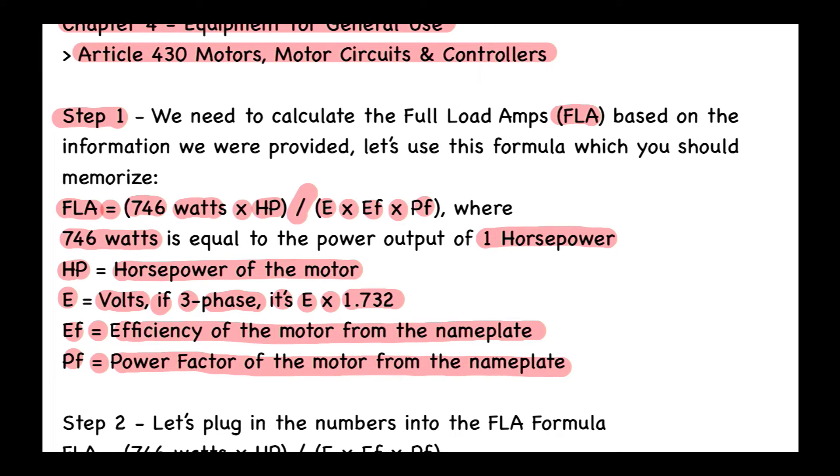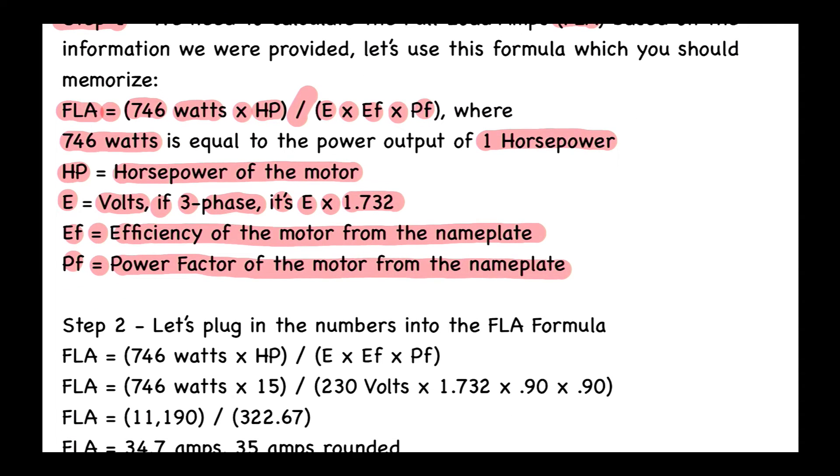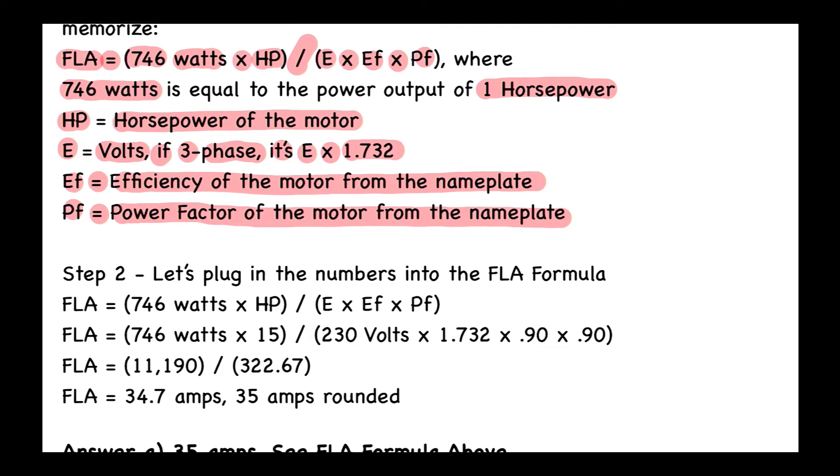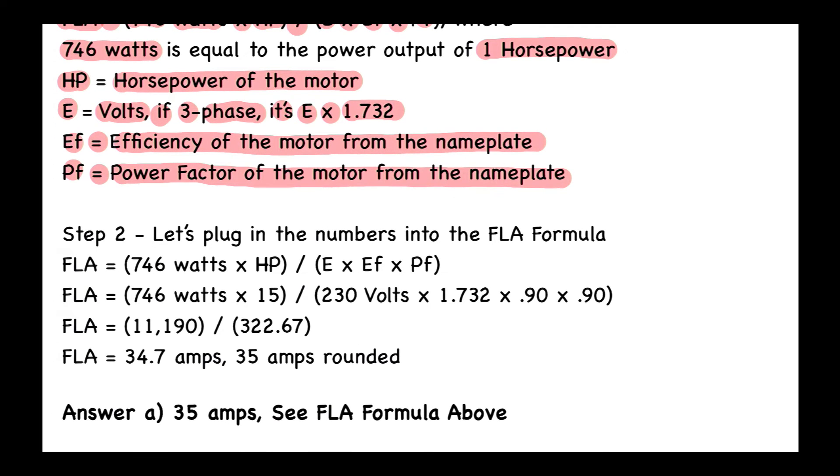Step number two: let's plug in the numbers into the FLA formula. We have FLA equals 746 watts times the horsepower divided by E times EF times PF. So now we get to the next line: FLA equals 746 watts times 15, that's for the 15 horsepower, divided by 230 volts times 1.732.